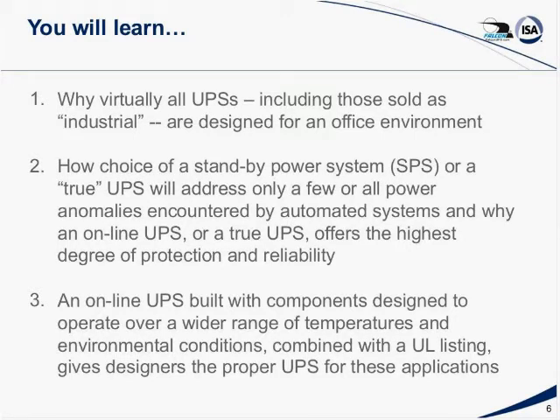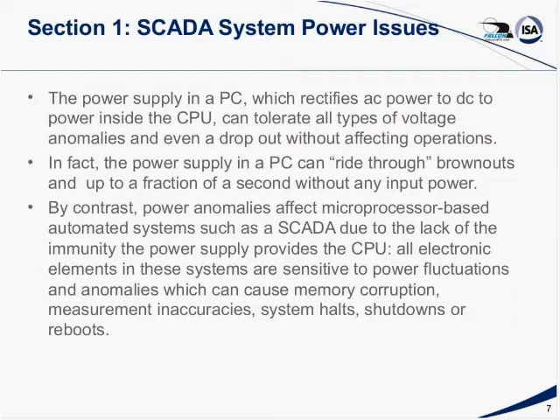Larry, could you tell us a little bit about what we would plan on learning today? Well, you'll learn why all UPS, all SCADA and most industrial equipment needs a UPS. You will also learn that most UPSs that are sold, even in the industrial area, are those designed for an office environment. Your choice of a standby power system or a true UPS addresses a number of power problems and power anomalies. We'll go into these in some later slides, but the only one that offers a high degree of protection will be a true online UPS. And the online UPS will be one that is built with components designed to cover a wide range of temperatures and the environmental conditions that you will find your applications in. These also should be UL listed, or if not UL, at least some third agency listed for the temperature ranges we're going to cover.